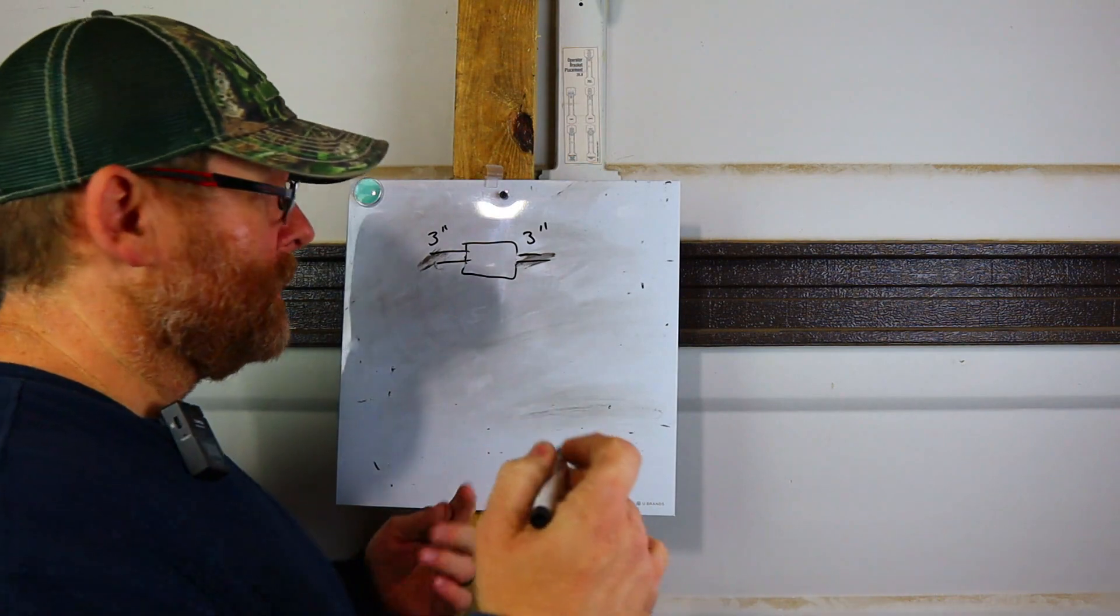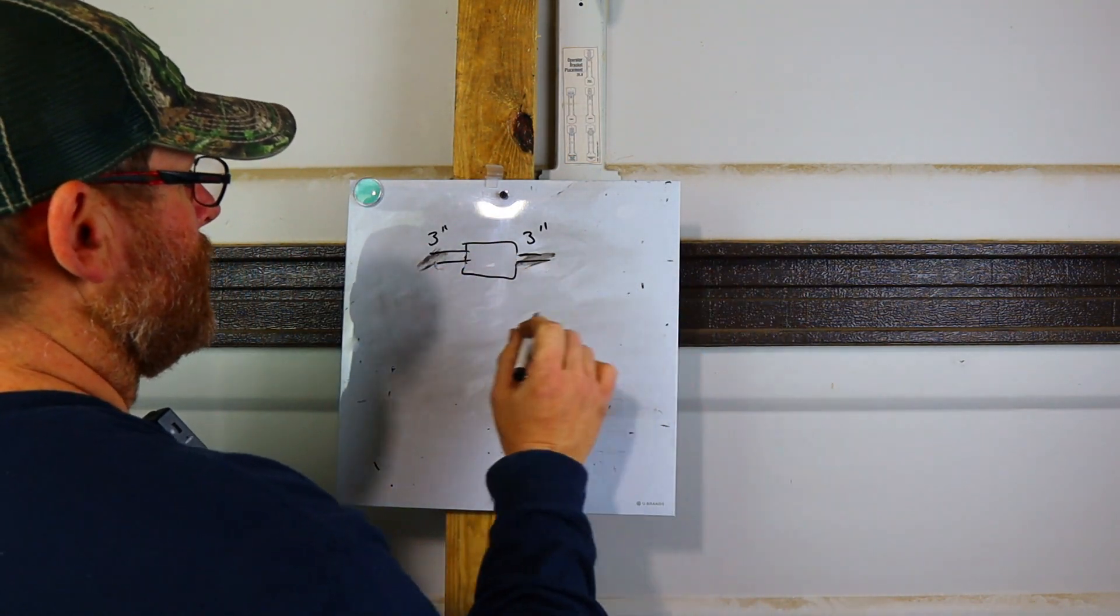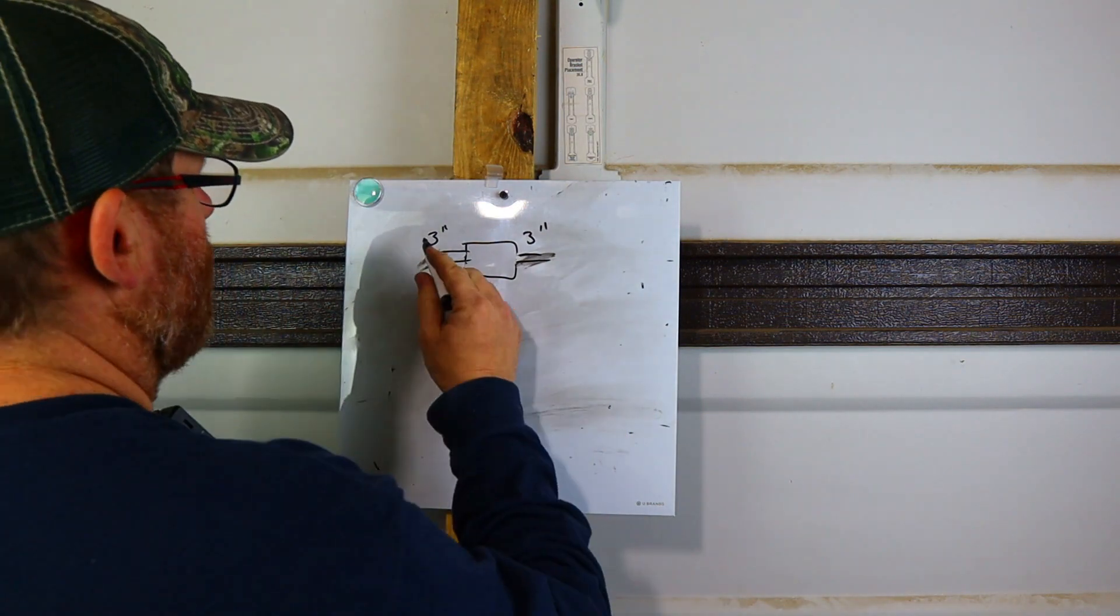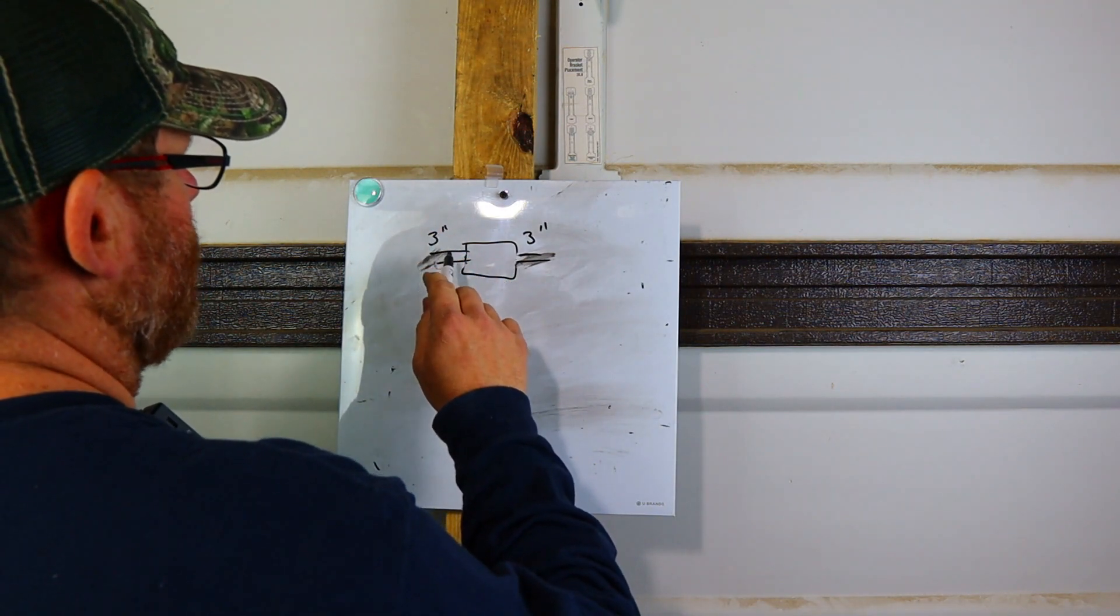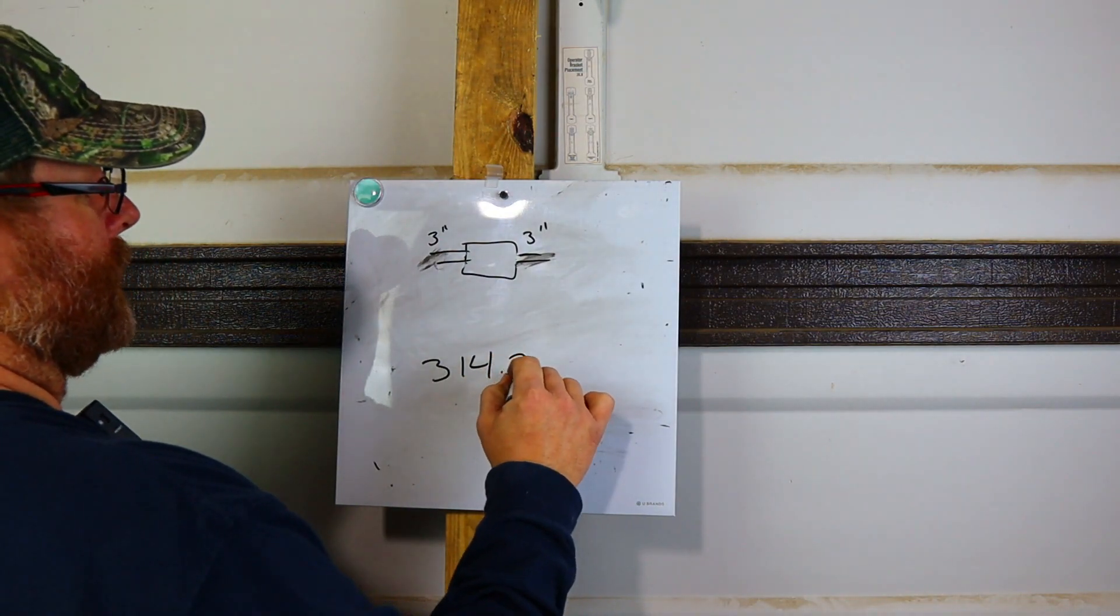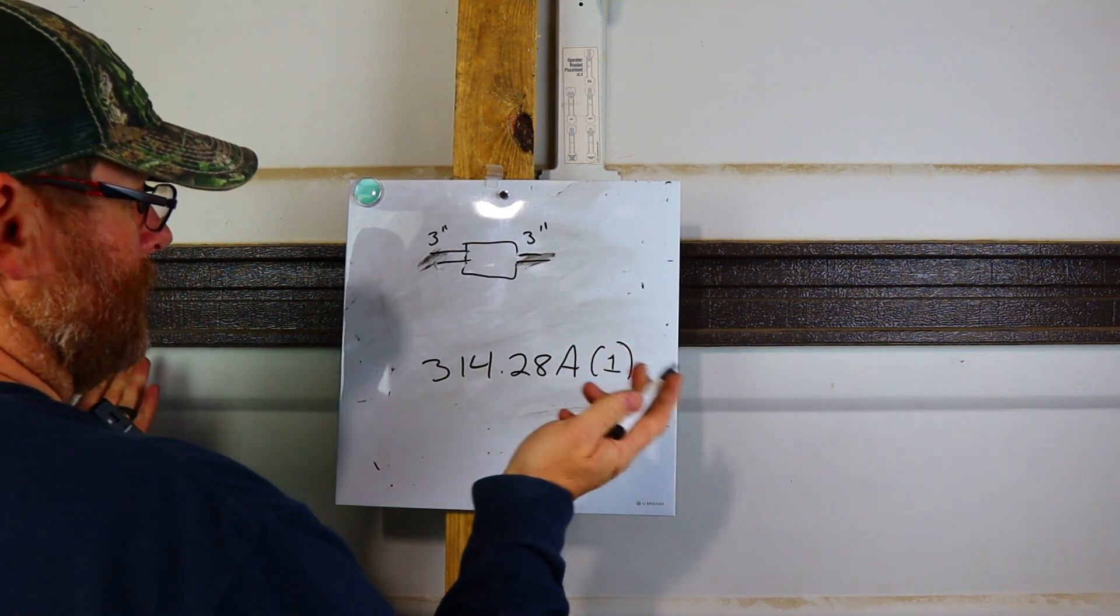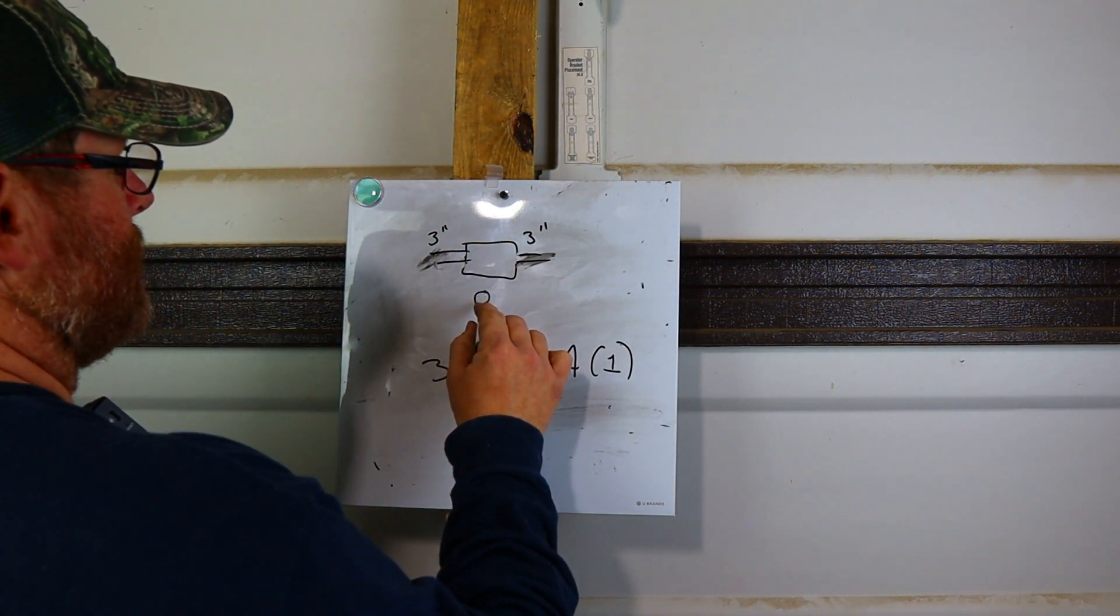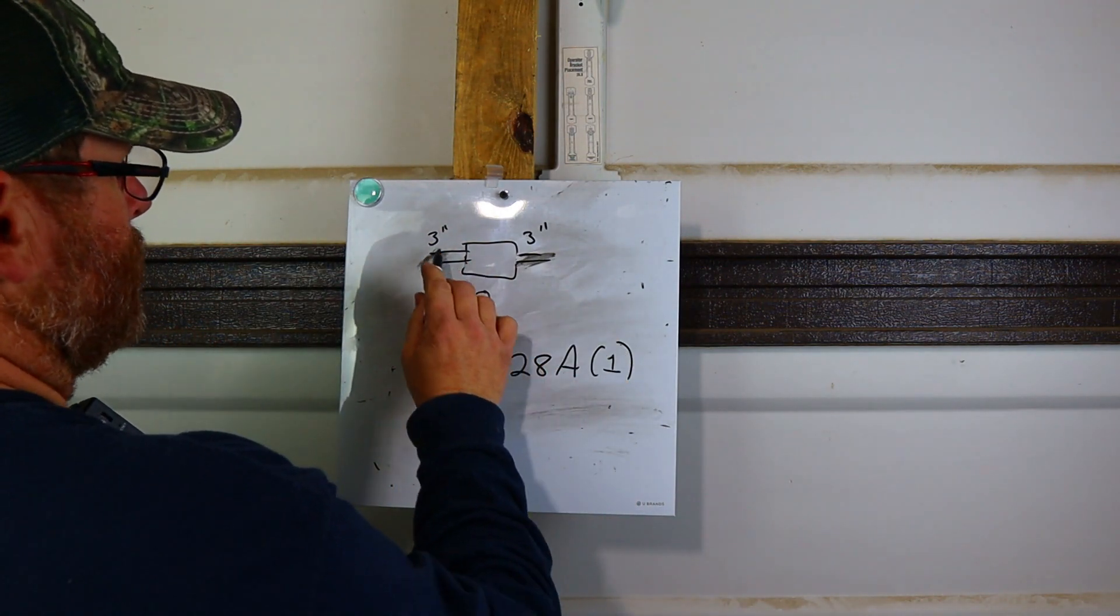This is going to be a straight pull because you see it's going straight in, straight out. Now this is your pull point. So what is the magic number? How do you figure out what size box you need? Well, it's easy. If you look in your code book at 314.28(a)(1), you go there and it tells you exactly what I'm going to tell you. The multiplier is 8. That's just what it is.